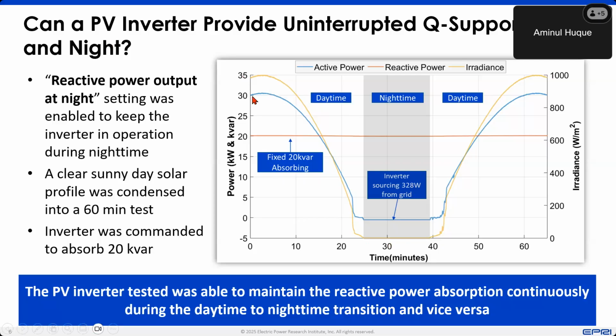The blue curve is showing the active power generation from the inverter, and we commanded the inverter to absorb 20 kVAR during this test period. So the command was go to reactive power absorption mode, and the target was 20 kVAR. So what we wanted to do, two things. One is, can it do it? Of course. The second part is, can it do it seamlessly? When you transition from daytime to night and then wake up from night to daytime the next morning, is there any interruption? Is there any period where it's not providing the reactive power support? So those are the main two objectives.